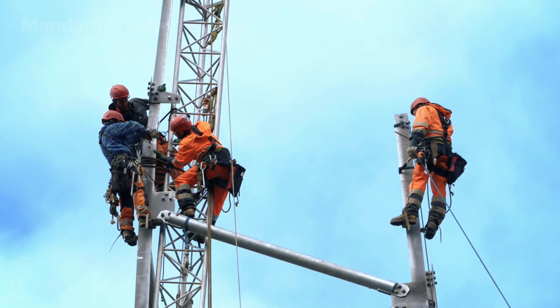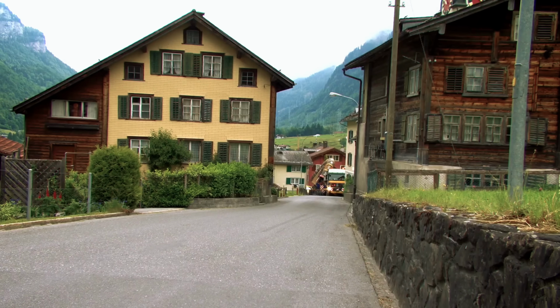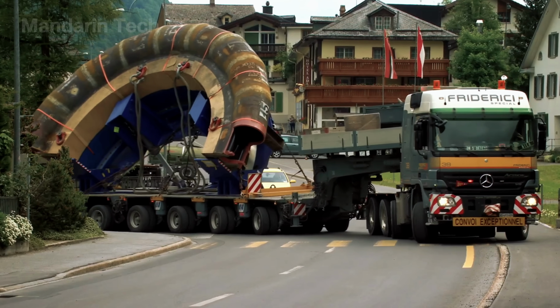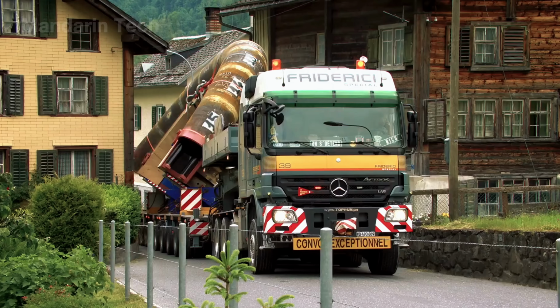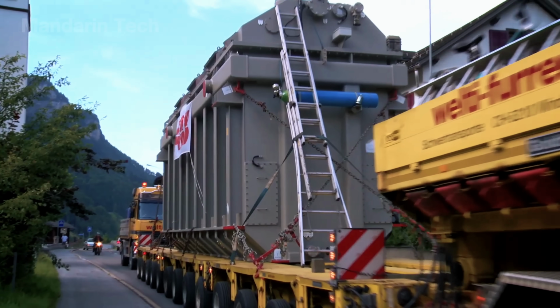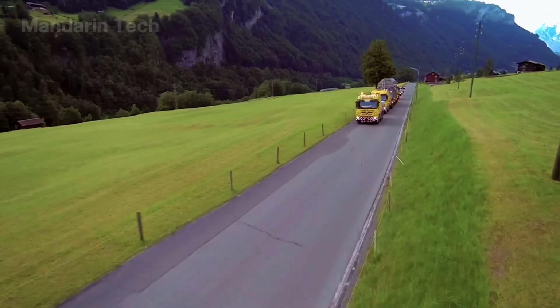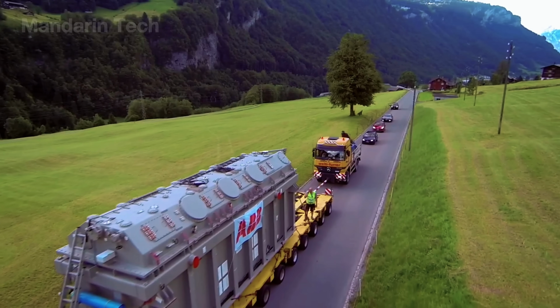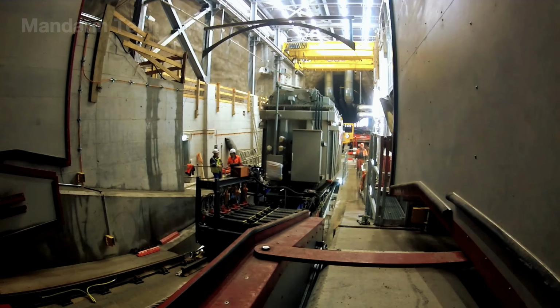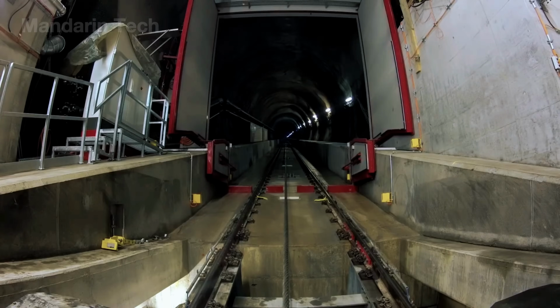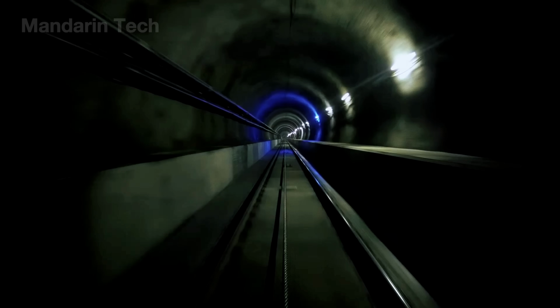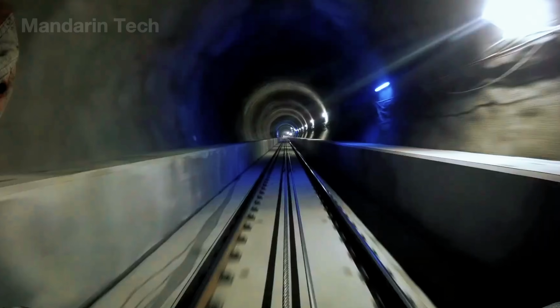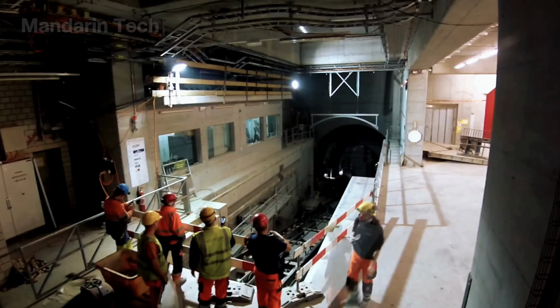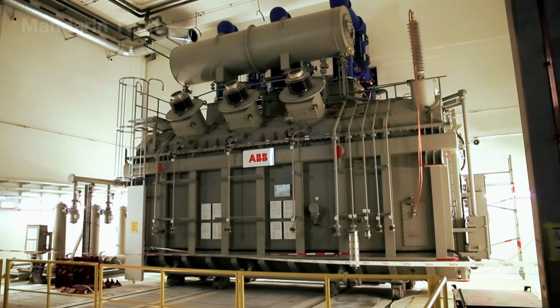In the steep Rocky Mountain terrain, much of the construction material had to be transported to the installation sites by helicopter. At the same time that the power line was being completed, another crucial logistical task was taking place in the valley below, transporting heavy equipment into the mountain. Some machine components, such as the spiral casings of the pump turbines, were far too large to pass through ordinary tunnels. The heaviest equipment, including the generator transformers, weighed up to 190 tons, far beyond the capacity of standard transport vehicles. As a result, these massive components were delivered directly into the powerhouse cavern through the newly completed access tunnel. This tunnel was specially designed with large dimensions and equipped with a 200-ton transport cable system, allowing heavy equipment to be moved deep into the mountain.